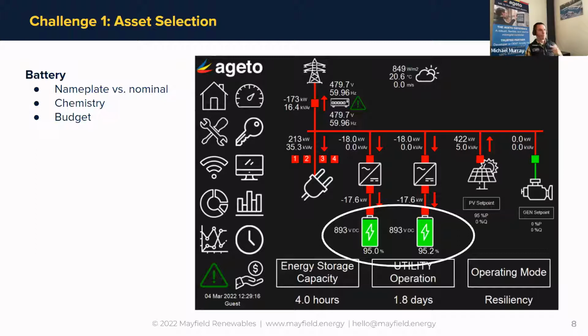But some of the parameters that affect selecting the batteries depend on what you're hoping to get out of the battery system. So one that we run into a lot is the nameplate versus nominal rating of the battery. Some batteries allow a full 100% depth of discharge, meaning if it's a 100 kilowatt hour battery, you can use a full 100 kilowatt hours of storage every day. Other batteries have a limited depth of discharge, so they typically have a recommendation to run between 10 to 90% or 10 to 95%. And with that limited range, your 100 kilowatt hour battery might only be 80 kilowatt hours. So just make sure you understand all the specifications when you're helping size a system.